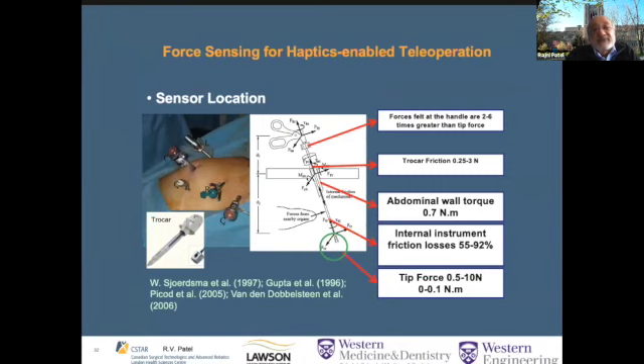So you can see that the forces outside of the body are of the order of about 2 to 6 times greater than the force at the tip. And so that means that if you put a force sensor outside the body, it would not really be very meaningful in obtaining an accurate representation of the interaction forces inside the body. So basically what this says is that you want to put force sensors as close to the tip of the instrument, or as close to where the tool tissue interaction is taking place, as possible.